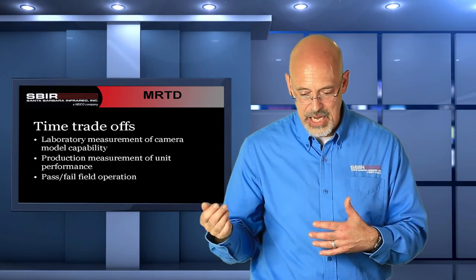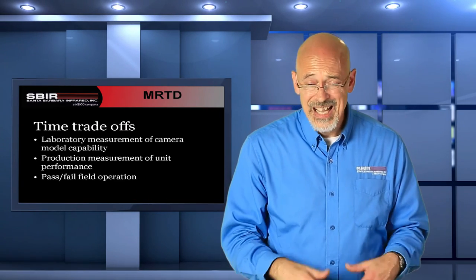So depending on the time trade-offs, you get a more accurate result. Clearly, if you're doing pass-fail, you're not going to get characterizing of the camera. But if you've got the time, you can do the more precise MRTD measurement. If you don't, you get by with a pass-fail criteria. That's the basic idea of MRTD. It gives you a good introduction to it, and when you talk about it, there's probably more details that we could have gotten into, but that's the good introduction to the MRTD test.